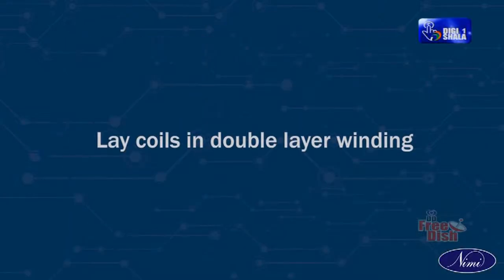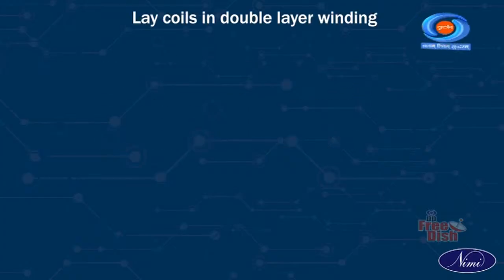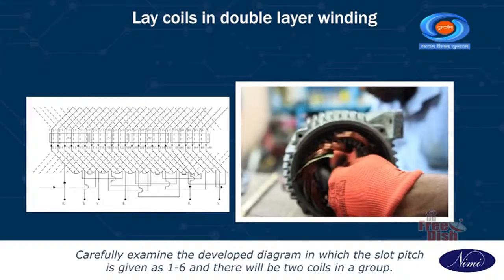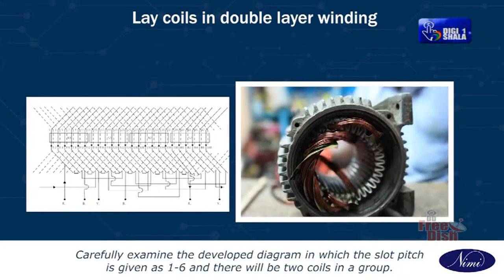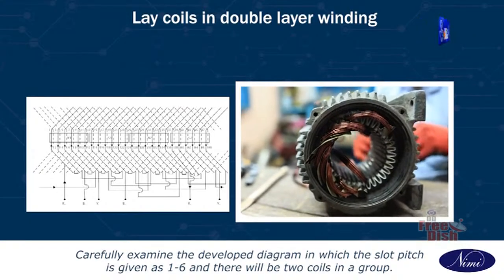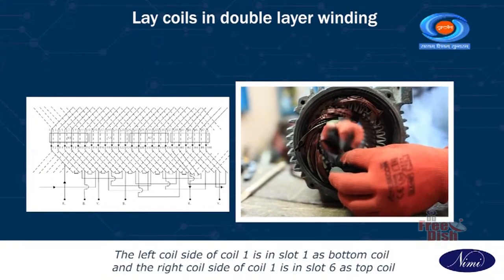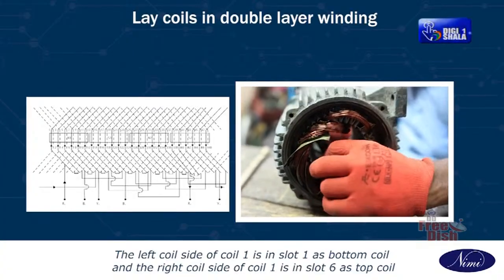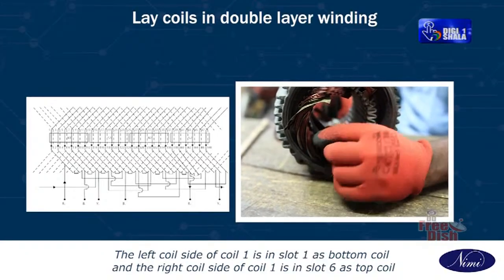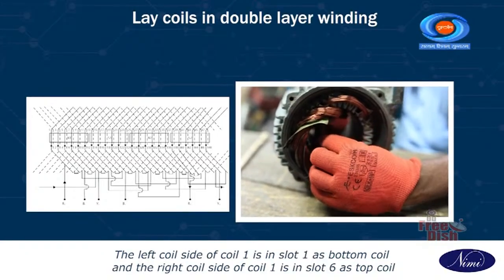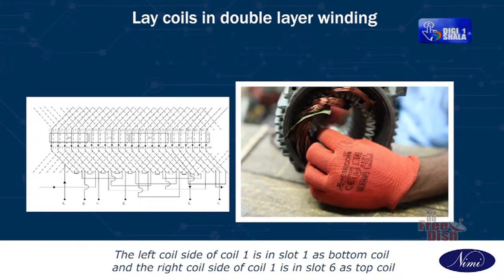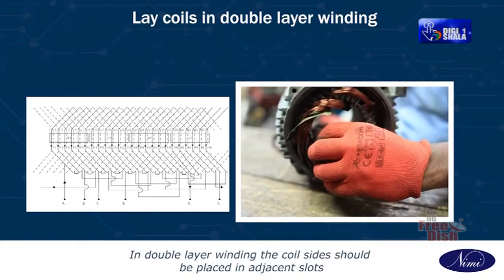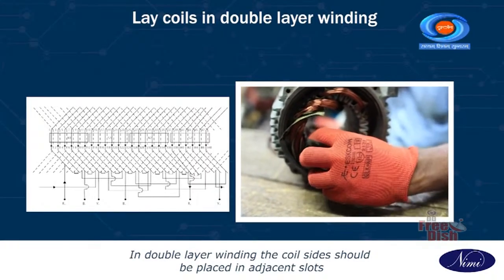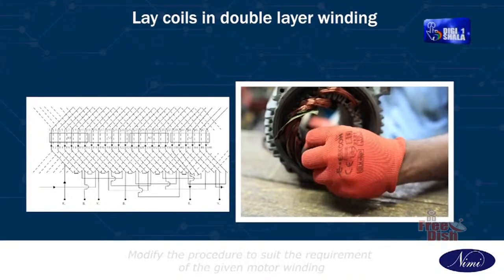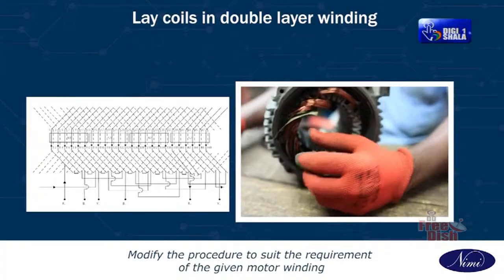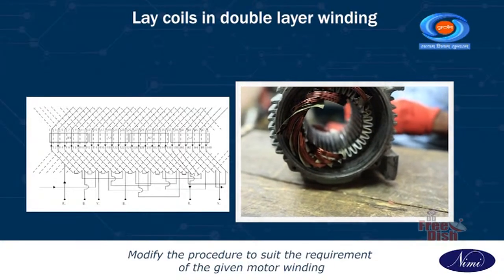Task 4. Lay coils in the double layer winding. Carefully examine the developed diagram in which the slot pitch is given as 1 to 6 and there will be two coils in a group. The left coil side of coil 1 is in slot 1 as bottom coil and the right coil side of coil 1 is in slot 6 as top coil. In double layer winding, the coil sides should be placed in adjacent slots. Modify the procedure to suit the requirement of the given motor winding.